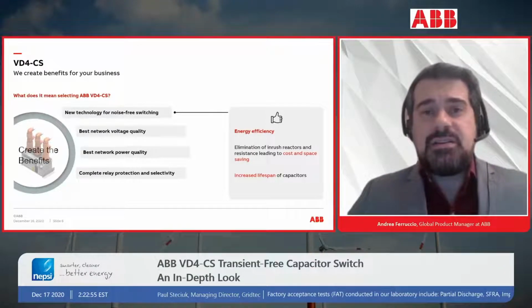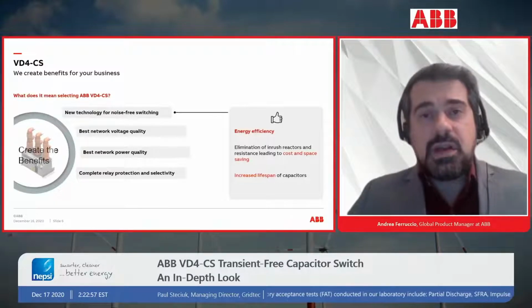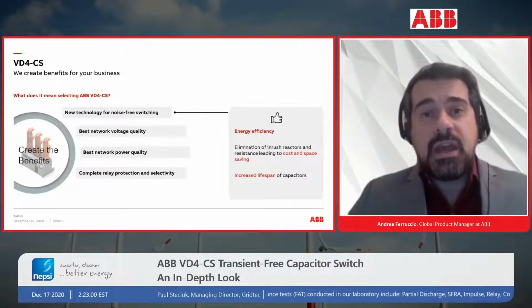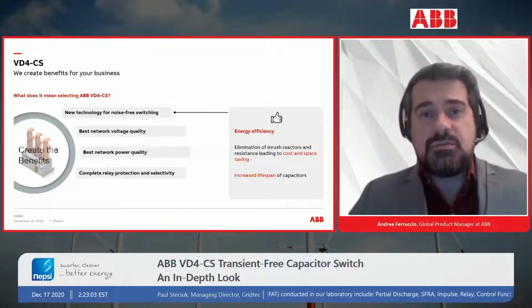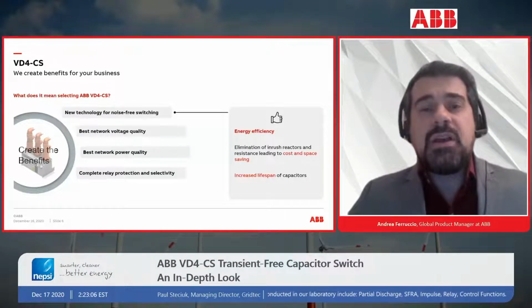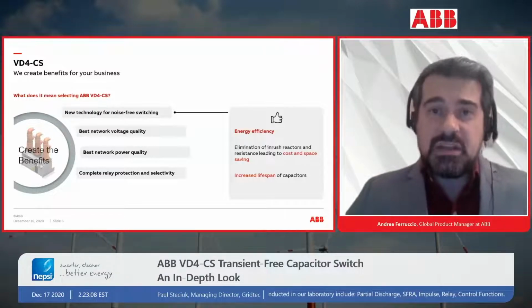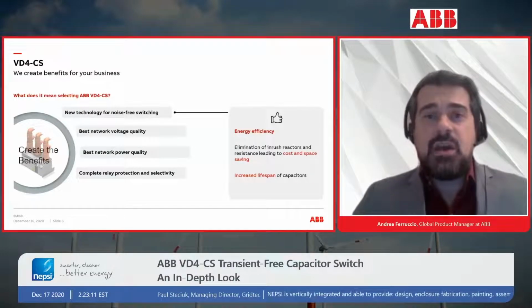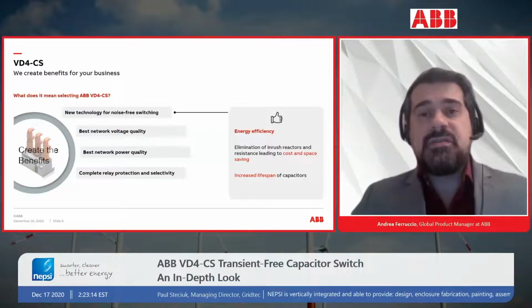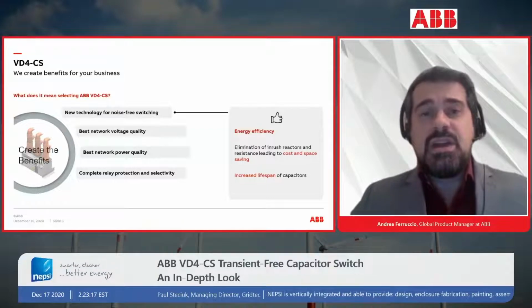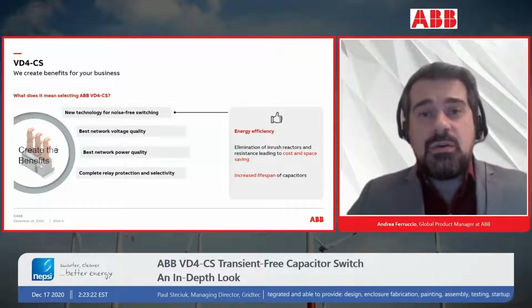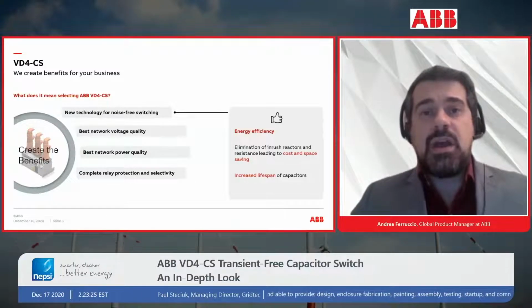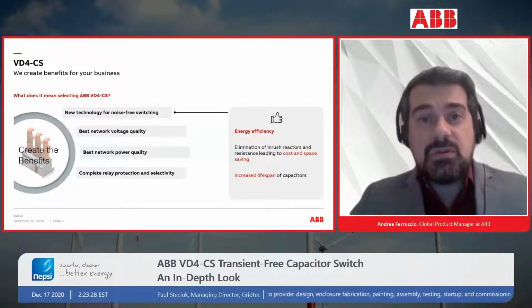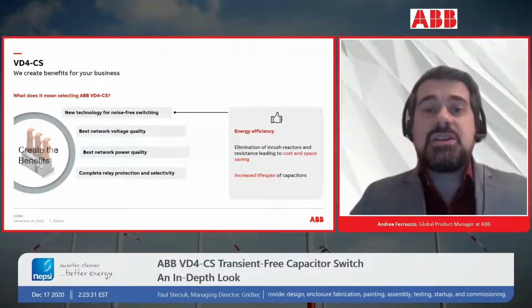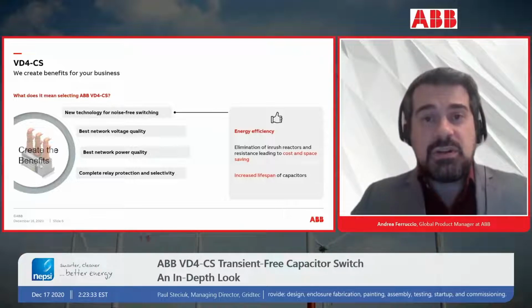We have identified your challenges using cap banks and switching cap banks, and now we can identify the solution. VD4-CS is the solution. Why? Because it is a complete circuit breaker, based on the innovative technology of noise-free switching, the synchronization. This means, exactly as anticipated before, the breaker knows exactly when it needs to open and close in order to eliminate such transients in current and in voltage.